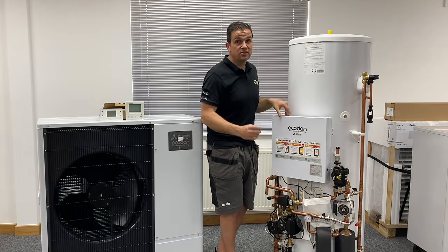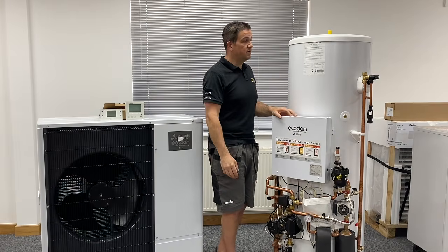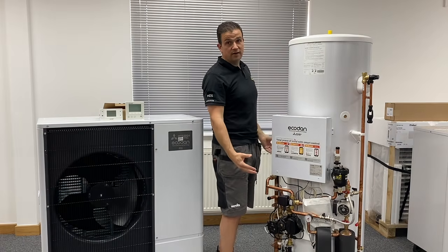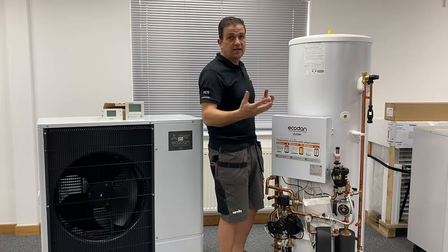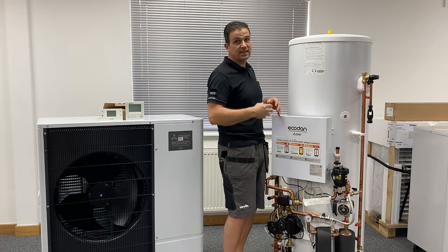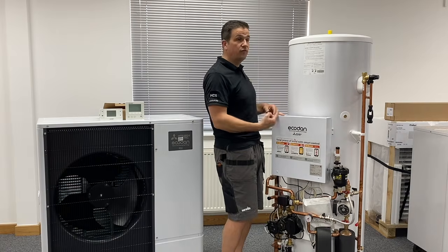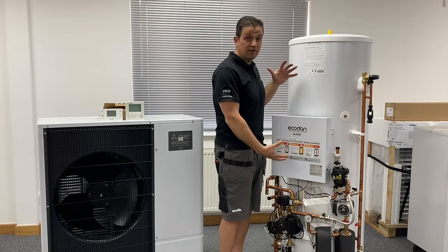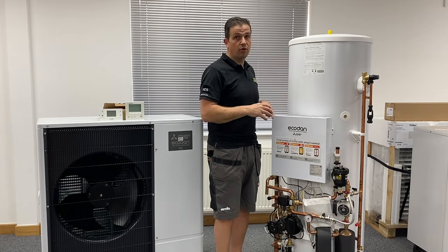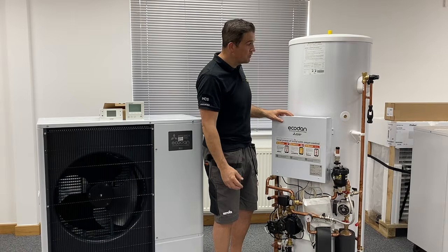So we've had to do what we call a third-party cylinder. Essentially you have a normal cylinder, or I say normal, it has to be heat pump ready. So it has to have a larger coil inside the cylinder to enable it to heat efficiently enough to give you appropriate hot water for a set amount of time.